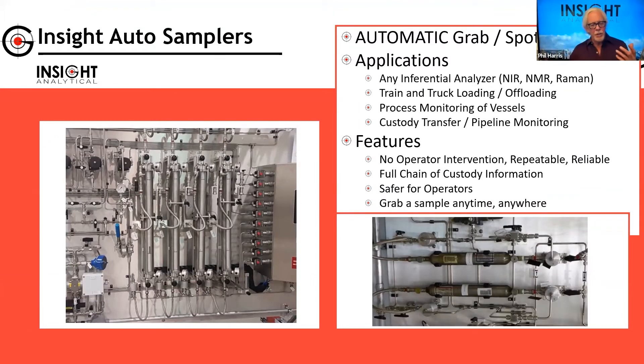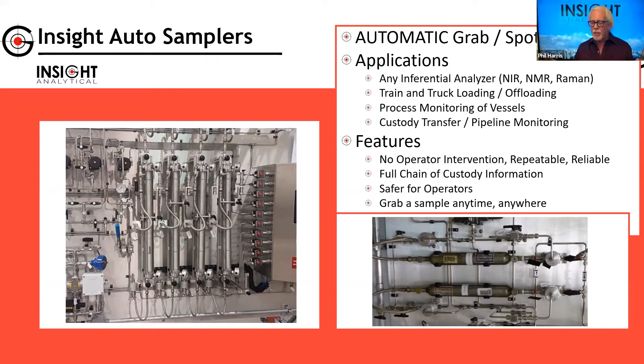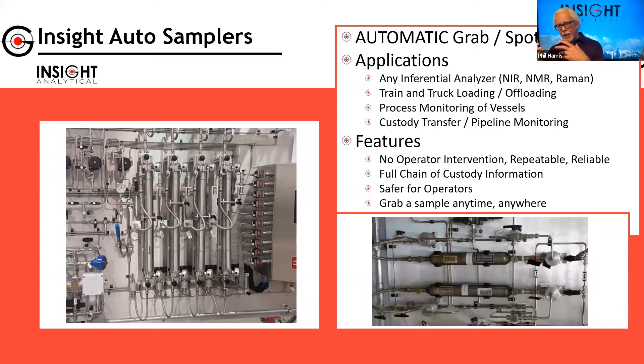Spot sampling and grab sampling is one of the most common methods we use to determine what's happening in a process. People go out and pull a manual sample — whether at a refinery, a gas plant, or on a pipeline — and send it to the lab for analysis. When we talked to lab personnel, they said the two biggest problems are: the person who pulled the sample didn't know how to do it properly, and for volatile liquids like propane or condensate, letting bubbles escape or not pulling at the right speed, or not allowing systems to purge long enough, all leads to a bad sample.